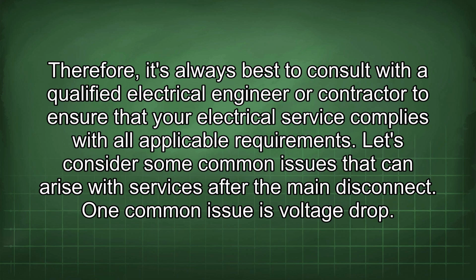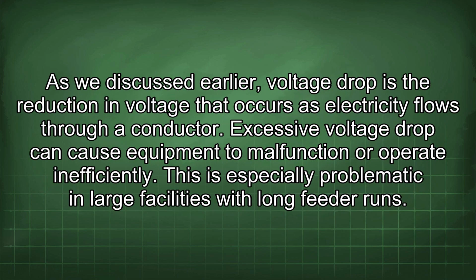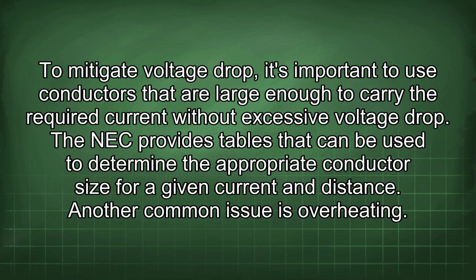One common issue is voltage drop. As we discussed earlier, voltage drop is the reduction in voltage that occurs as electricity flows through a conductor. Excessive voltage drop can cause equipment to malfunction or operate inefficiently. This is especially problematic in large facilities with long feeder runs. To mitigate voltage drop, it's important to use conductors that are large enough to carry the required current without excessive voltage drop. The NEC provides tables that can be used to determine the appropriate conductor size for a given current and distance.